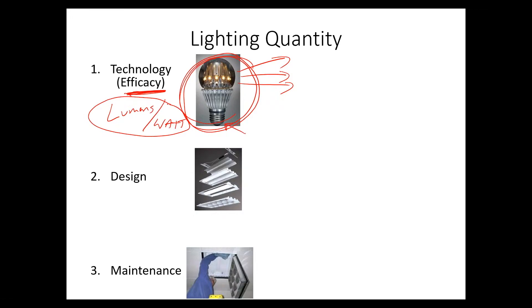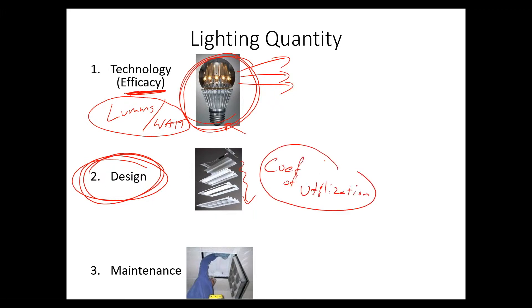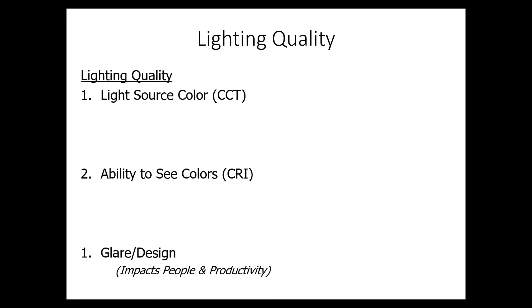Then the light has to escape the fixture, which is where design comes in. The light has to get through all these baffles and get to the target. There's a term called coefficient of utilization, which is somewhat like the delivery efficiency, and this relates to the fixture. Finally, the third thing is maintenance — if we clean the fixture more often, we get more light out of it.